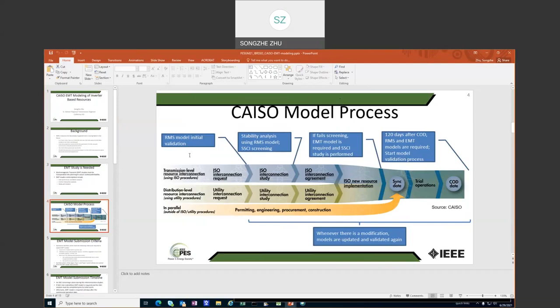For the EMT model, at least for the ISO, we don't collect the model at the very beginning of an interconnection request. The reason is that most of the interconnection requests will not come to the finish line. Also, at the early stage of an interconnection request, they haven't decided on the inverters and the manufacturer yet. So those are quite speculative at the beginning, and throughout the interconnection process, pretty much every project will change their inverters several times. That's why we don't collect the EMT model upfront.